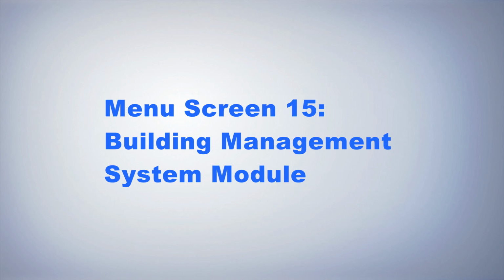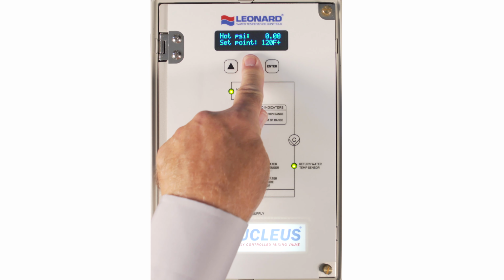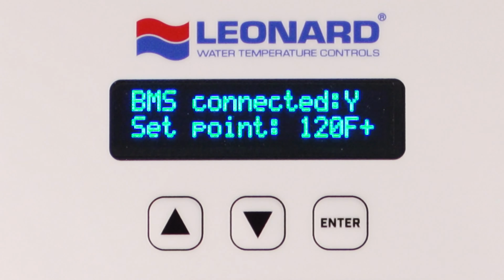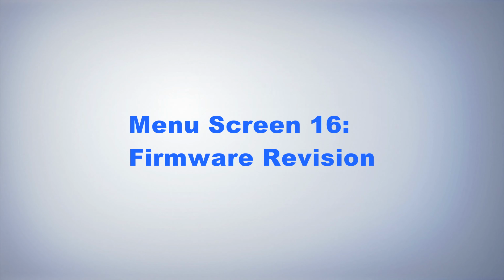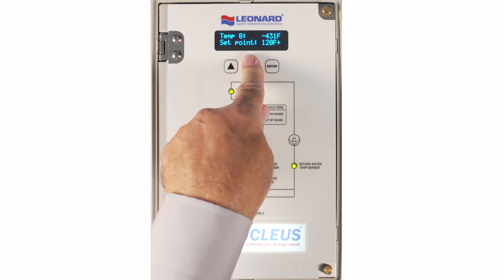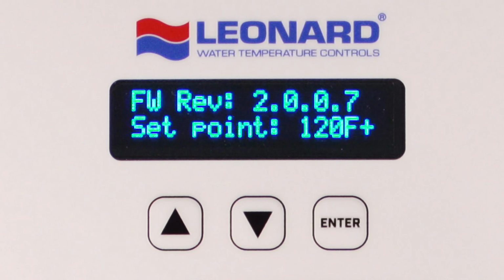Menu screen 15. Building Management System Module. Pressing down 15 times displays BMS connected, no or yes. In order for this to be Y or yes, the control box needs the following conditions. The Leonard supplied processor needs to be installed on the main printed circuit board. This screen confirms that the protocol converter is communicating with the main PCB. If N is displayed and a processor is connected, make sure the module is installed properly. Menu screen 16. Firmware Revision. Pressing down 16 times displays Firmware Revision. This screen shows the current version of firmware loaded into the Nucleus processor. It may be used for reference and troubleshooting.